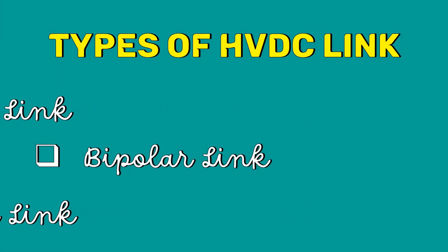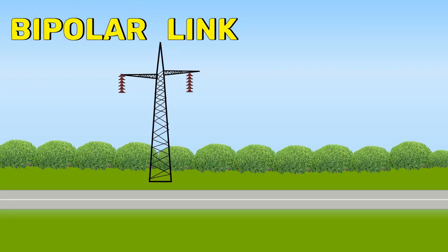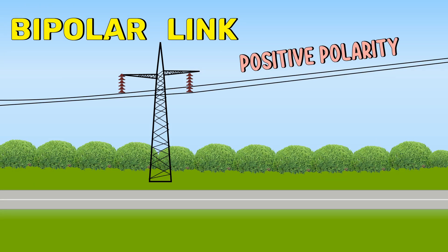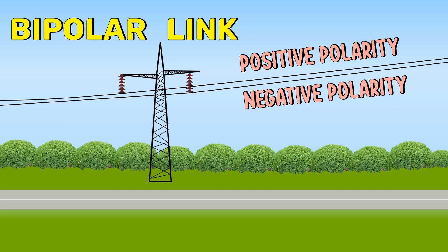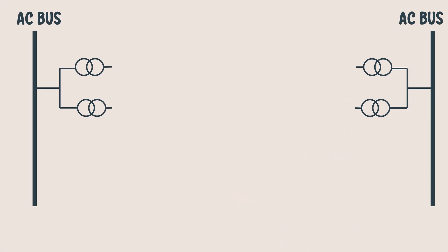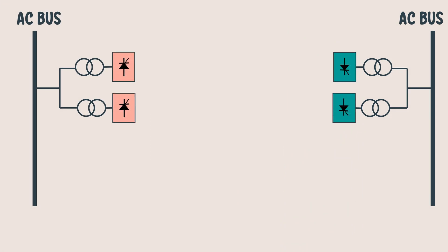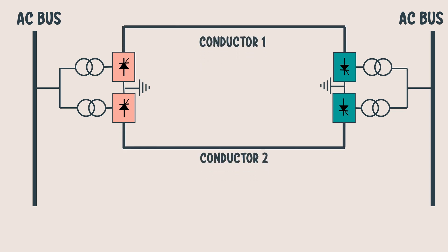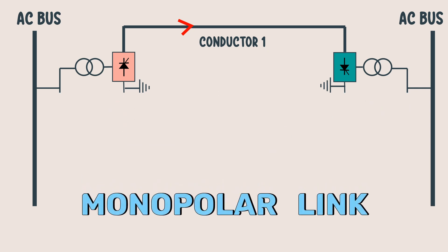The next one is the bipolar link. Bi means two. As the name indicates, this link has two conductors — one positive and the other of negative potential of the same magnitude. At each terminal, two converters of equally rated voltages are connected in series on the DC side. The junction between the converters is grounded. If the current in the two conductors is equal, then the ground current is zero. If one conductor has a fault, the link is converted into monopolar mode, meaning the other half of the system continues to supply power.